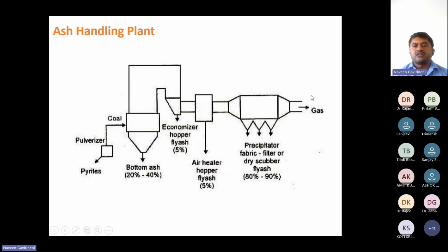At the end, the gas temperature is around 120 to 130. There is one concept for coal, that is the sulfur dew point temperature. So we can reduce the flue gas temperature, but not beyond the sulfur dew point temperature. Why? Because if you reduce the temperature below the dew point temperature, there is a chance of eroding the duct arrangement, and the ID fan impeller will also collapse. For that purpose, every OEM, while erecting and commissioning the boiler, will supply the sulfur dew point temperature.